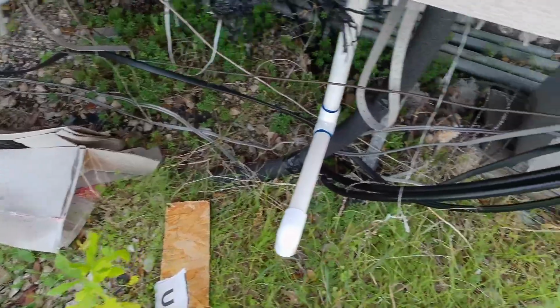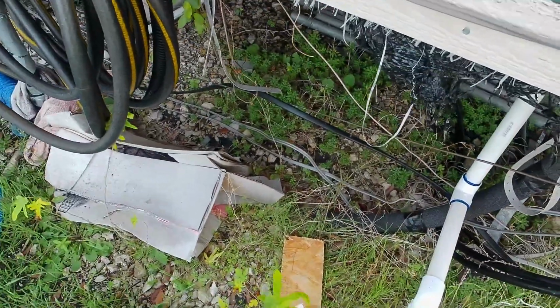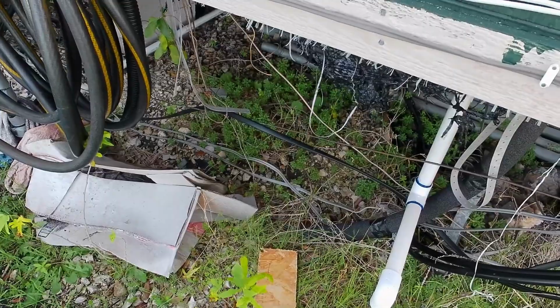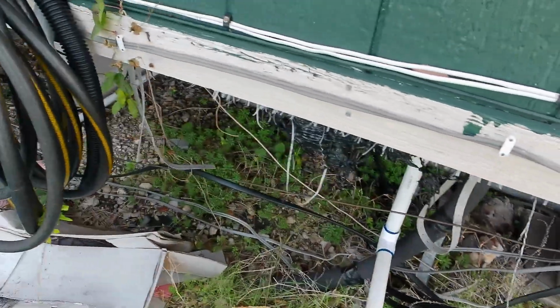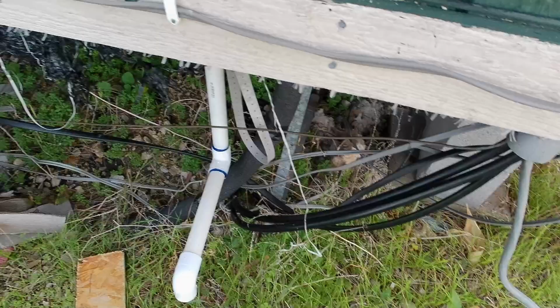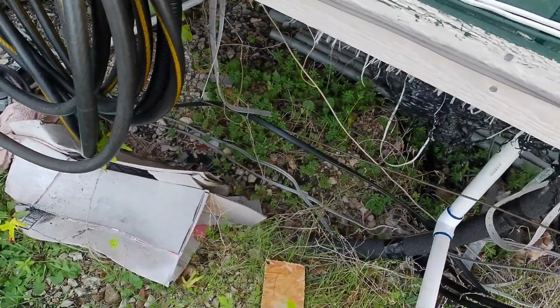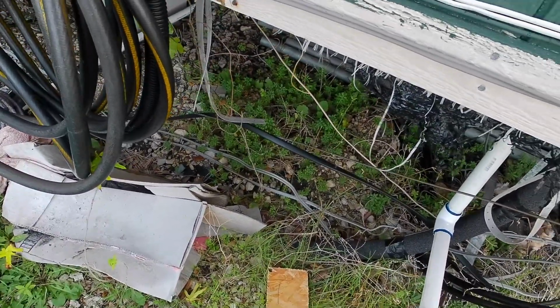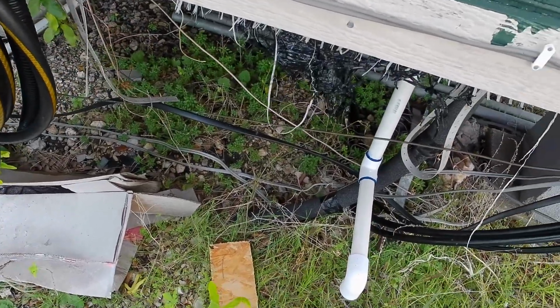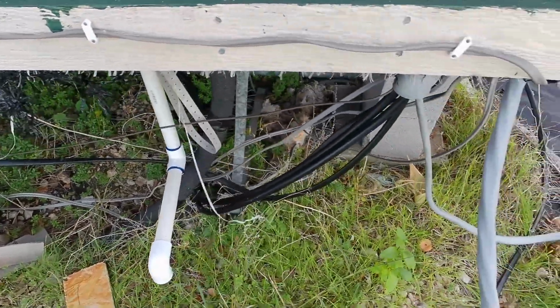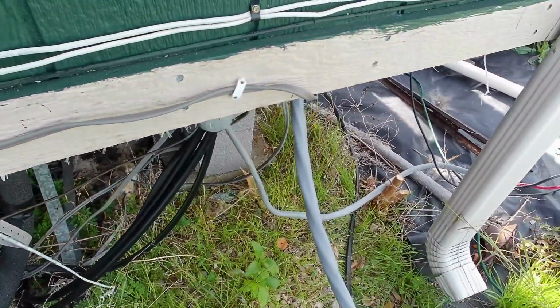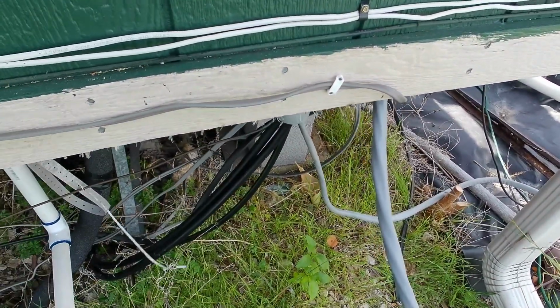And they come up, and you're allowed to do this. This gray stuff is not Romex, it's made for direct burial underground, and it can be run outside of the home, even though the code doesn't require it because this is considered a crawl space. I'm not required to have special cable, but I went ahead and went the extra mile and got that special rated number 12-2 wire, so I could have a little tougher wire outside.